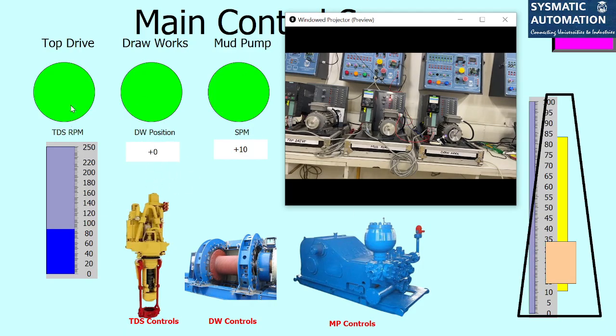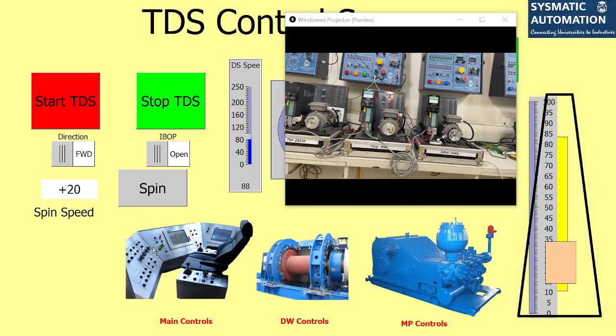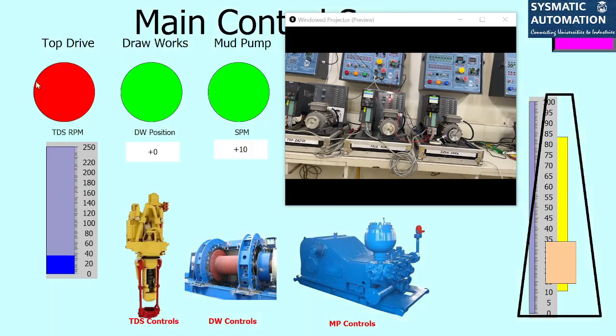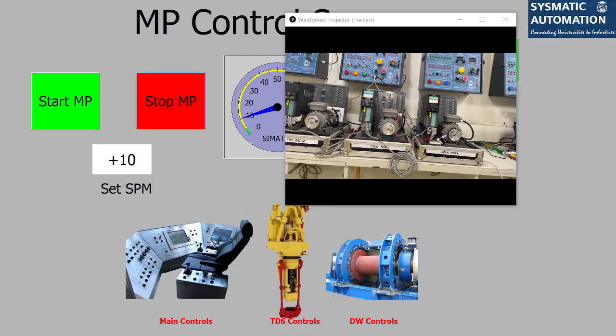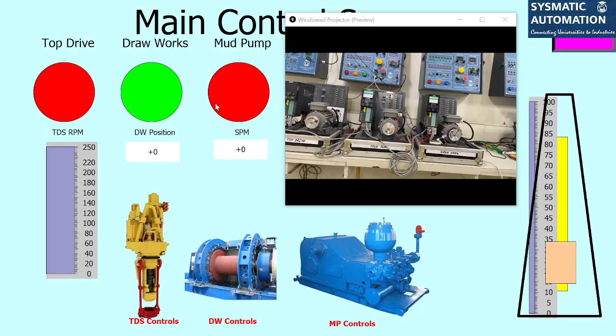See, I have made simple graphics here. So if you know how SCADA and PLC programming work, then you can make similar screens. If I go to the top drive screen and stop it, then go back, the top drive is showing red here. That means the top drive is stopped. The mud pump is still running. If I go to mud pump, stop it, and go back to the main screen, it is stopped.